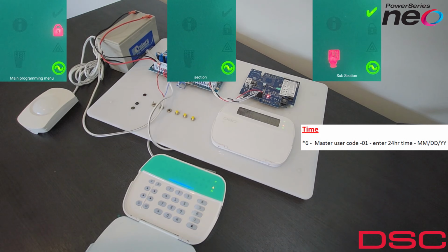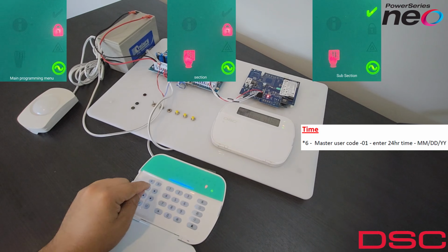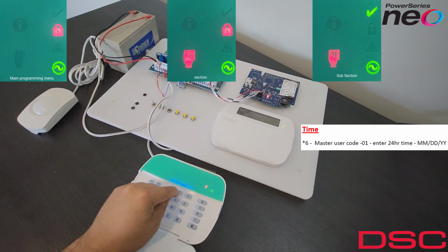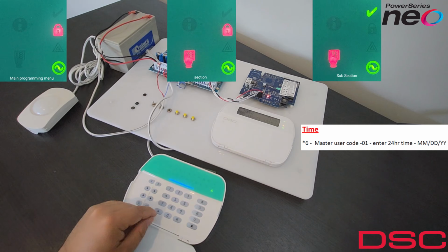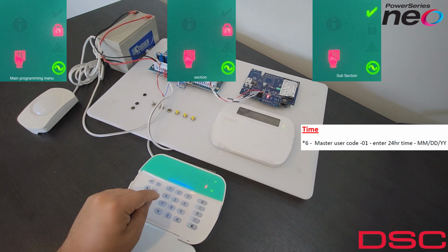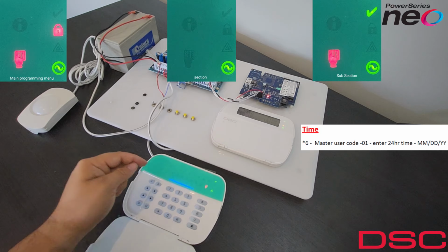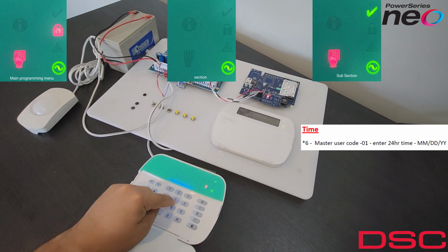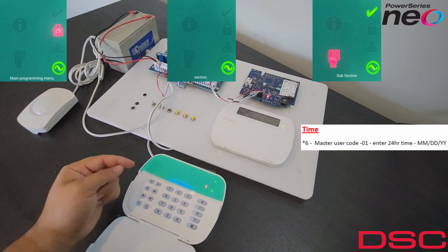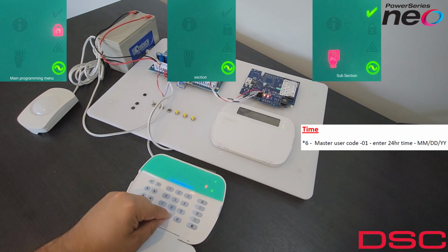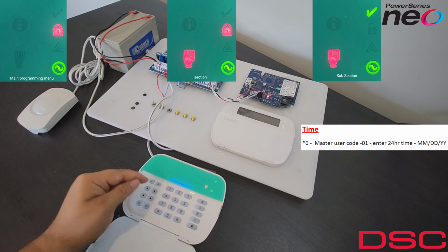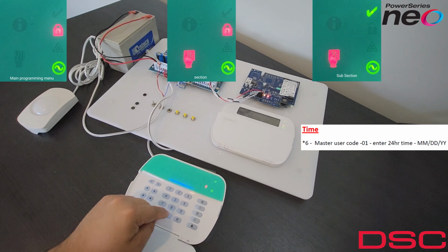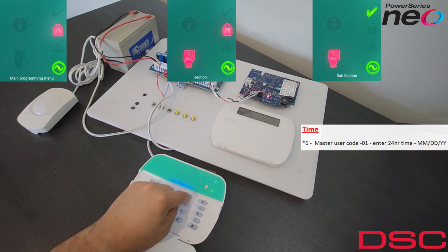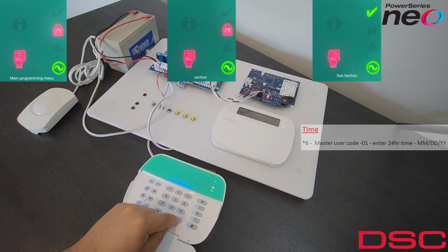Okay, once you've booted out your panel, what you want to do is set your time. So we want to go to *6, you go to 1, 2, 3, 4 for your master user code, and then we want to go to 0, 1, and then you're going to punch in your time. So for me, I'm just going to say it's 10:52. Then I'm going to do my month, so the 2nd, and then my date, 10th, and then my year, 23. Then hash out.